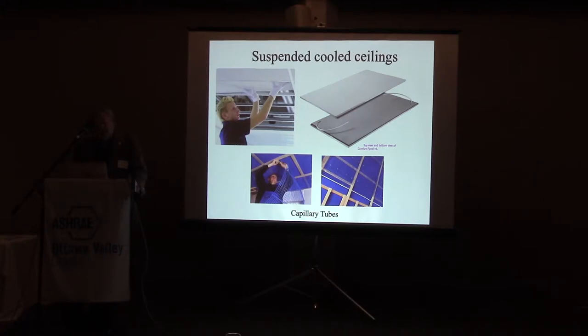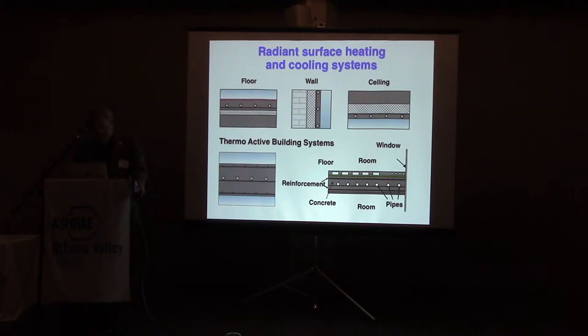When we now go to the systems where we have embedded some of the piping for the transfer of energy, we normally distinguish between systems which are insulated from the main structure of the building, like most typical floor heating. You have pipes embedded in the screed, but it could also be in wooden construction, and then it's insulated from the main structure of the building. Similarly, it can be used for wall systems and ceiling systems. So it's a little different from the suspended ceiling panels, because you don't have any air gaps here. And that's important for how we determine the capacity. For those systems, we can use about the same formulas, but for suspended ceiling panels, it normally requires testing at a test place to get the data on the heating and cooling capacity.